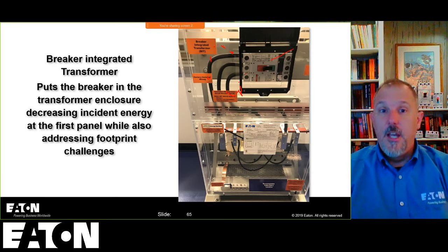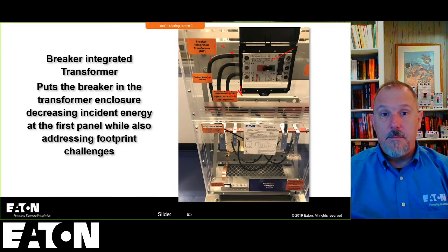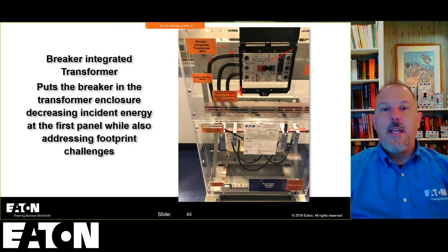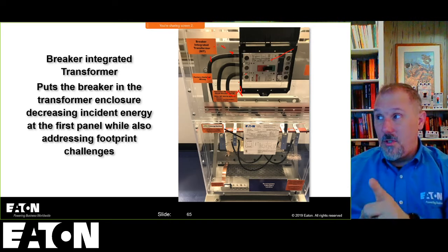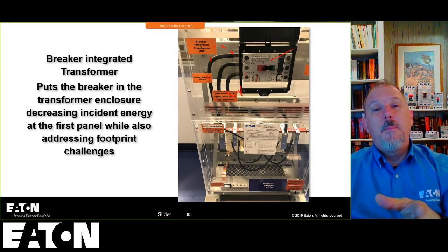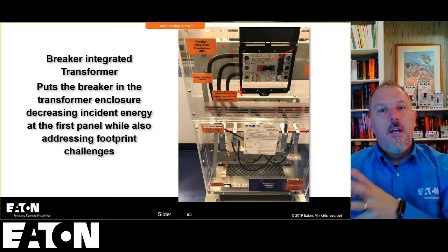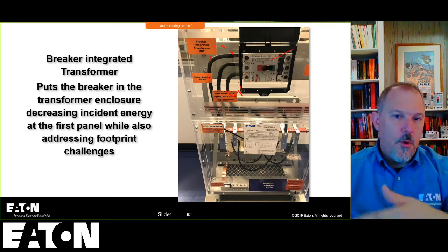and that's going to get you in front of exposed. The arc flash calculation is going to be based upon the primary overcurrent device. At that point, your arcing current is going to be greater, and you'll have a better chance of being in the instantaneous region of that main breaker. But actually, no, you don't have a better chance. I guess you could. It's going to depend upon the difference between your inrush current and your arcing current. Remember, your arcing current is going to take into consideration the coils and all that other good stuff.